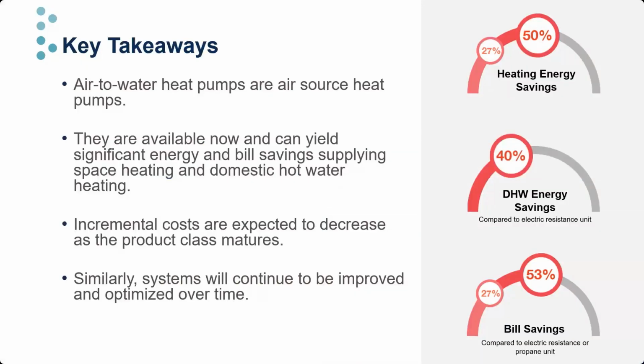So just to reiterate, air-to-water heat pumps are air source heat pumps, but they just differ in their distribution medium. While relatively new to American markets, there are well-established solutions for hydronically heated homes internationally. Dozens of models and configurations are currently available, and they can fit virtually any residential application in Minnesota homes. The systems we observed brought space heating energy savings of 6,300 to 17,300 kilowatt hours per year, or about 27% to 50% in predicted heating energy savings in similar applications.